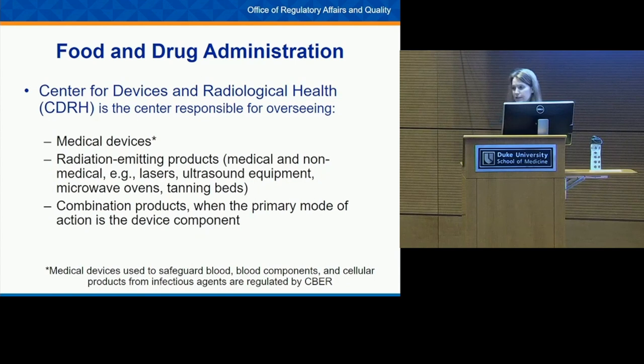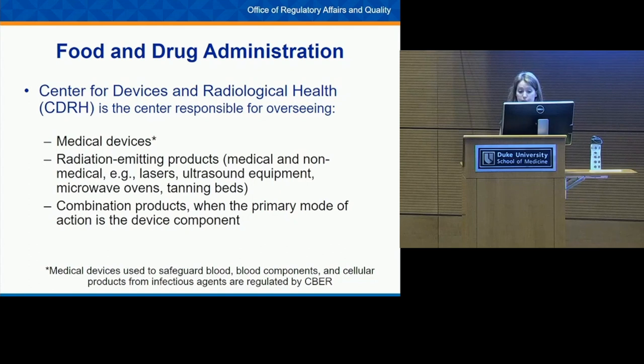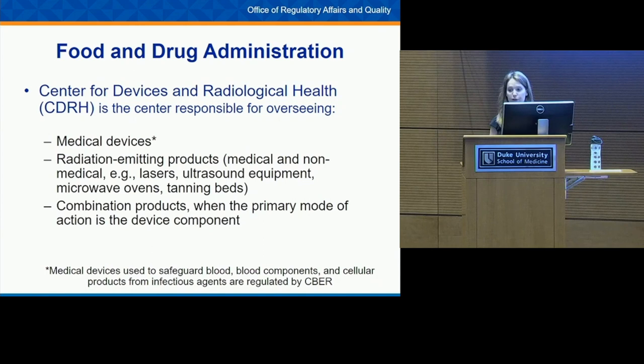For the most part, medical devices are overseen by the Center for Devices and Radiological Health (CDRH) at the FDA. They oversee most medical devices, radiation-emitting products (medical and non-medical, such as lasers, ultrasound equipment, microwave ovens, and tanning beds), and combination products when the primary mode of action is the device component. For example, drug-eluting stents are overseen by CDRH because FDA determined the stent portion is the primary mode of action.